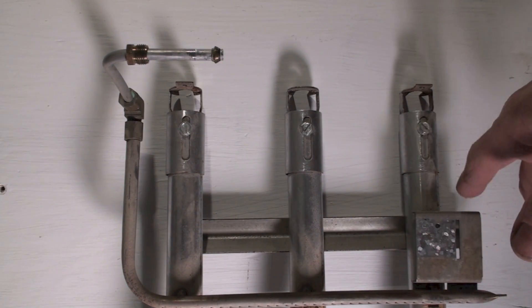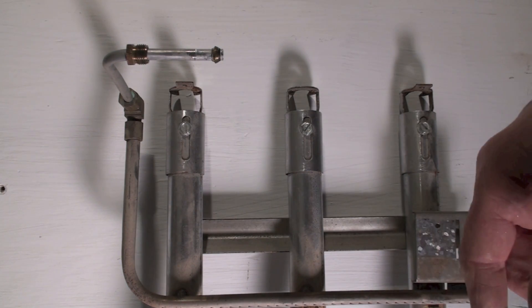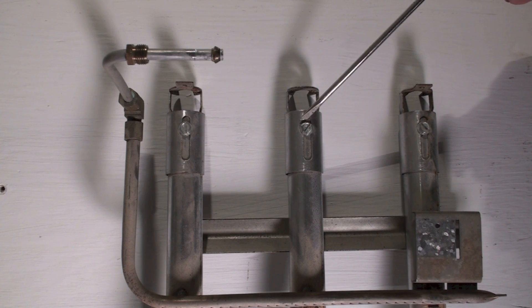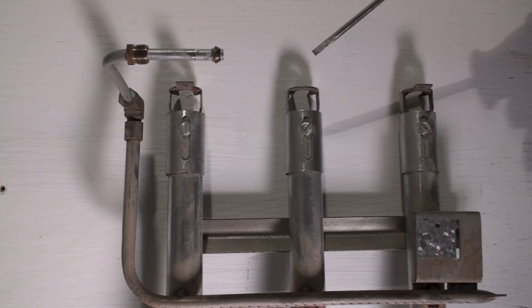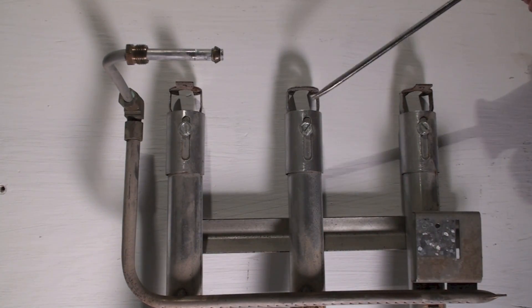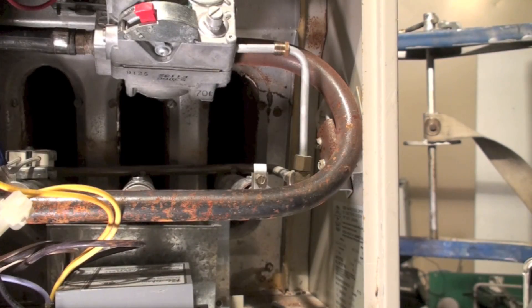An awful lot of installers would never adjust these things. The newer ones don't have adjustments on them, but these things are open as wide as they'll go. There's a little bit more in the slot but they're not going to open up any farther than they are, so it doesn't look like when this was installed they were ever adjusted. We'll adjust these in with the flame burning.